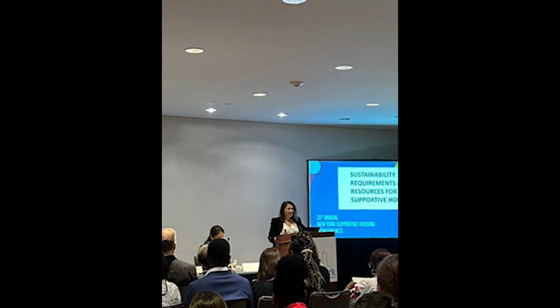Be mindful of schedule, especially with Con Edison in New York City. If they have to do street work or anything else to upgrade your service, that can have very long lead times. Another annoying budget factor: these are occupied buildings in the Bronx with existing Con Ed accounts, but with new service they're requiring deposits. So even with multiple existing accounts at the address, we're still paying not huge amounts, but about $10,000 in deposits we didn't anticipate.